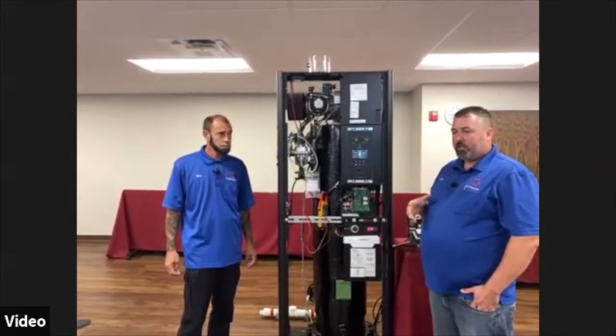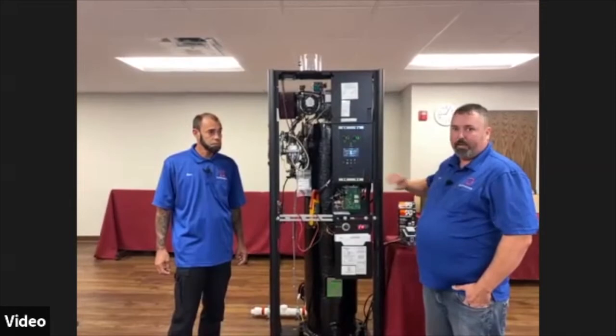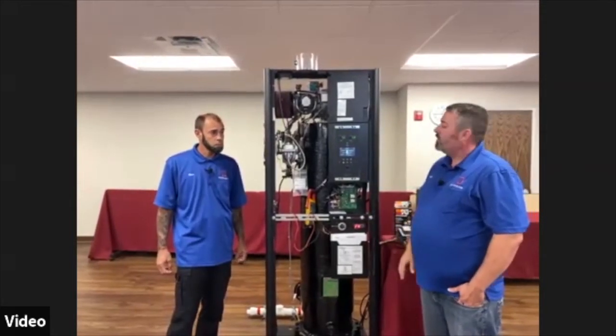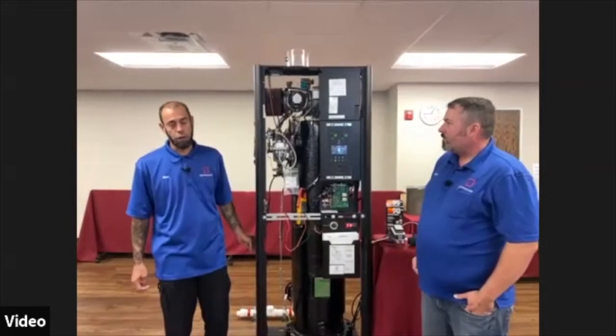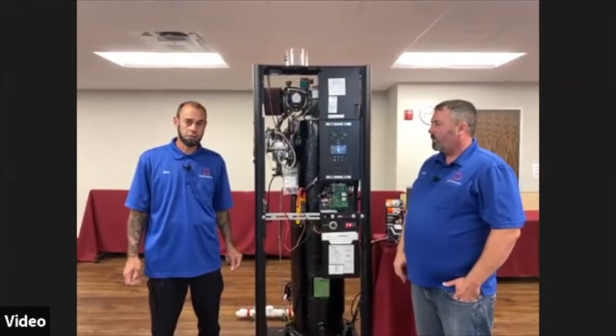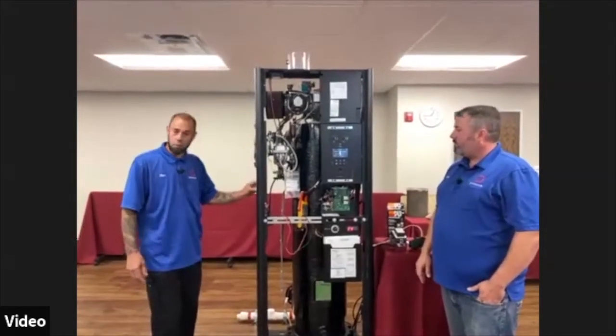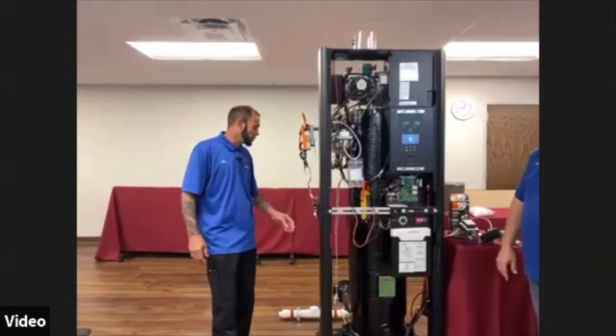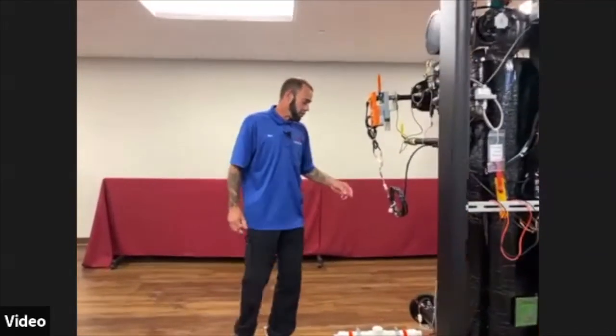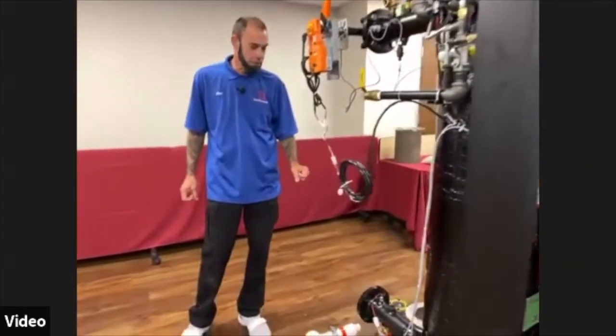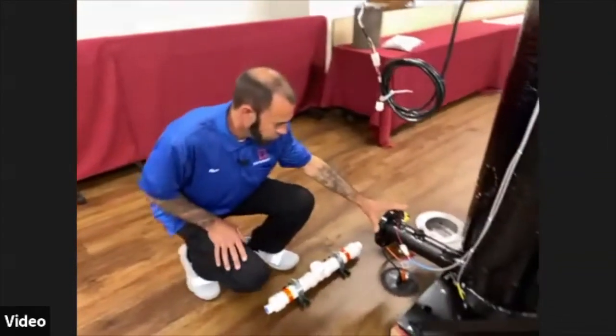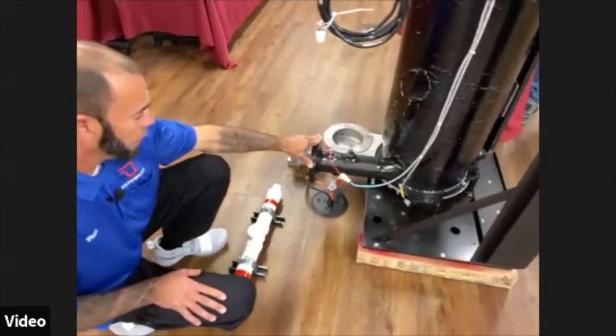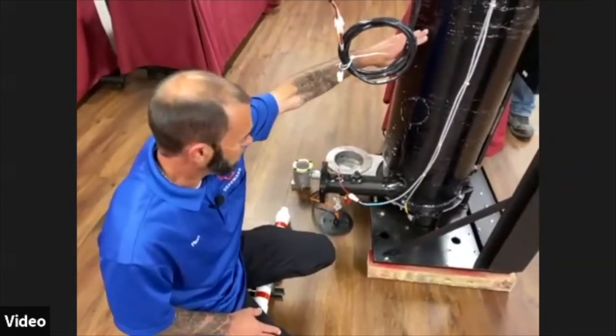It's one-way communication. AERCO can only read. They cannot send anything to the boiler. They can't change anything. They can only monitor. It's important to note that that would require an Ethernet cable connection as well from the building. And the third thing that the Platinum would have differently than the standard Benchmark with the Edge control would be a dual return system. So when we were at the back of the boiler the last time, we noticed we only have one return down low. In the Platinum, we would have a second return above this.